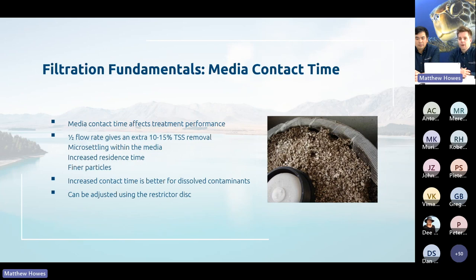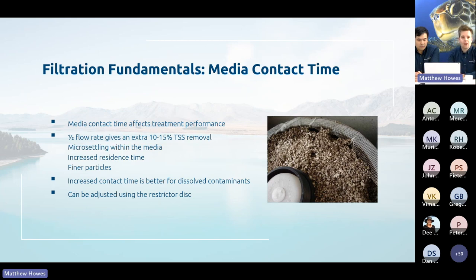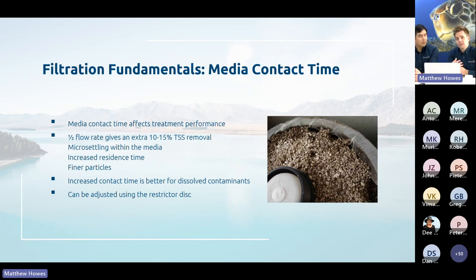Media contact time is important for metal removal where chemical interactions occur, but also for TSS removal. Testing found that reducing the flow rate to half, even with perlite, gives an extra 10–15% TSS removal. This is achieved by increased residence time within the media, which promotes micro-settling of sediment within the media, capturing finer particles. Increased contact time also benefits dissolved contaminants. Flow through the cartridges is adjusted using restrictor disks.